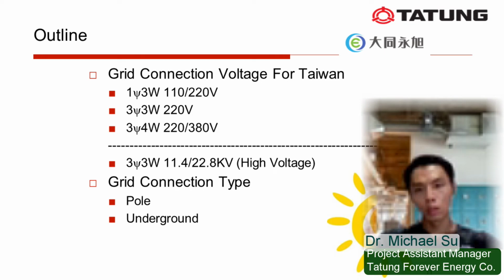Here is the information regarding the grid connection voltage. As we have previously mentioned, we use the single-phase 3-wire transformer for the current lower than 220 volts. If the equipment can handle higher voltage, we use 3-phase, 3-wire or 4-wire transformers to handle the current higher than 220 volts. The 3 wires are the R, S, and T wire, and the additional wire of the 4-wire one is the N wire. Either the 3-wire one or the 4-wire one, there will always be an E wire connecting to the ground.